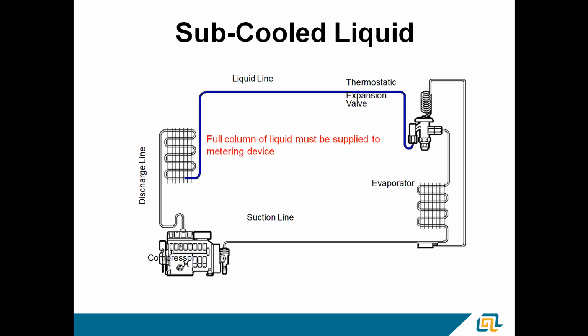Subcooled liquid should never be cooler than the air temperature that's being used to cool it. In other words, if you're working on an air conditioner on a 72-degree day and you measure your liquid line temperature and you find your liquid line temperature down around 65 or 60 degrees, you got a restriction in there somewhere, because the refrigerant should never be cooler than the air that's getting pulled across that condenser to cool it off. So you find that really cold liquid line, you probably have a restriction in the condenser. Maybe it's just a plugged liquid line filter dryer or something like that, but it is definitely cause for concern, something to keep an eye out for.